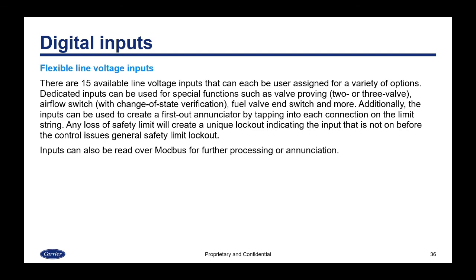Dedicated inputs can be used for special functions such as valve proving, airflow switch proving, fuel valve end switch, proof of closure, and more. Additionally, the inputs can be used to create a first out annunciator by tapping into each connection on the limit string. Any loss of safety limit will then create a unique lockout indicating that the input is not on before the control issues the general safety limit lockout. Inputs can also be read over Modbus for further processing or annunciation if you're using a Modbus connection.